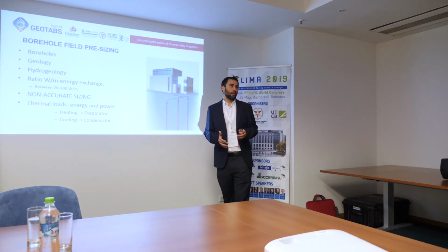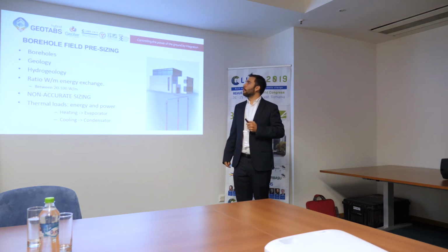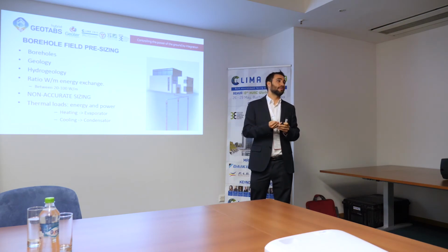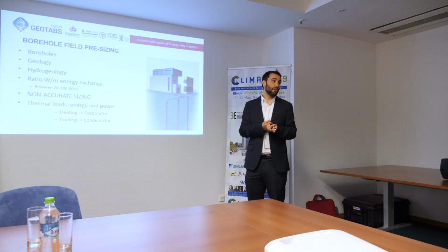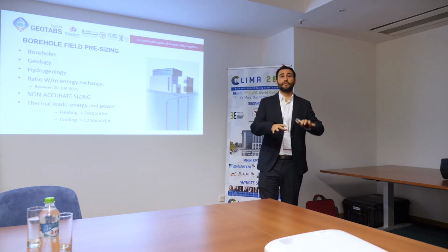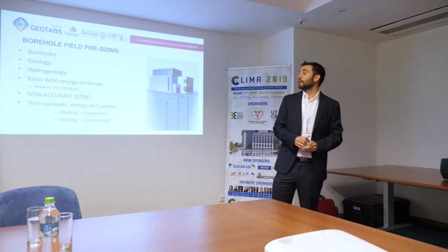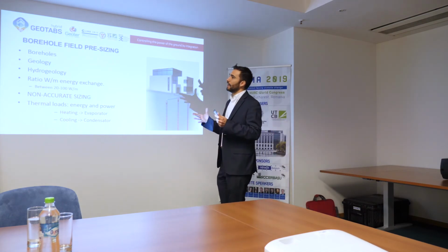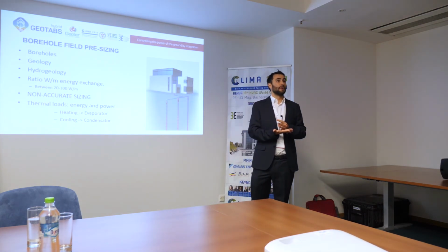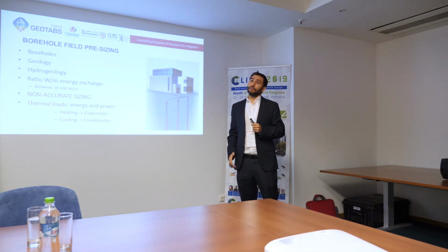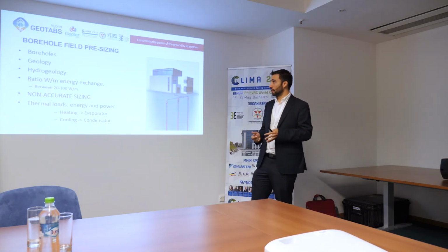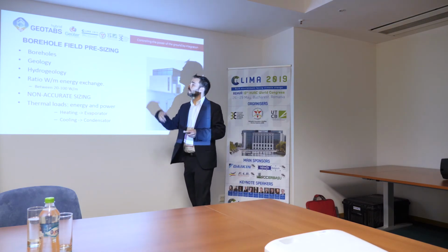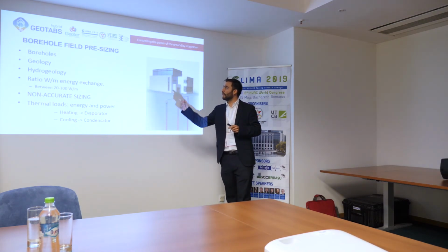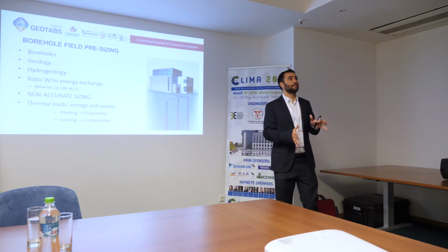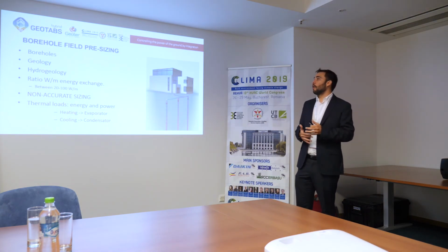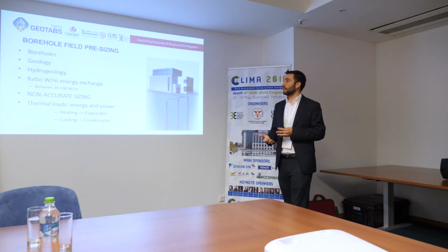If we have the building and we want to design the borehole field, first we have to consult the geology and hydrogeology of the area. We have different maps of the different zones in the different countries, and you can analyze which materials compose the subsoil and if groundwater flow exists or not. With this information, we can estimate a ratio, watts per meter, of energy exchange, and in an initial pre-sizing we can estimate how many meters I have to drill for my installation.